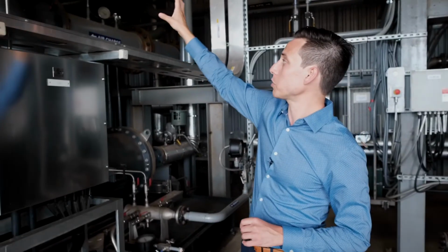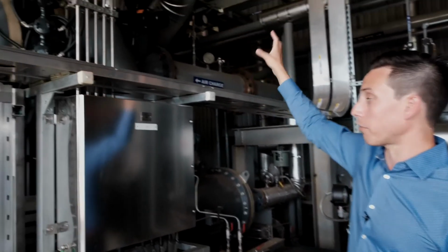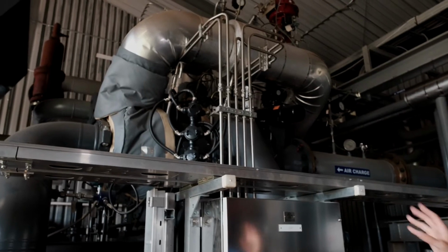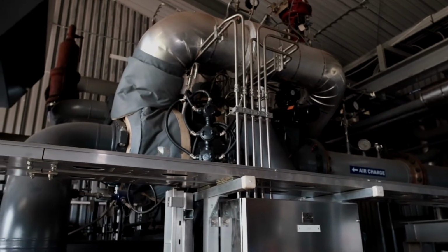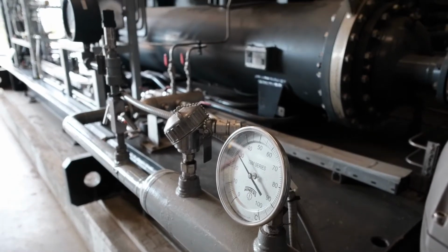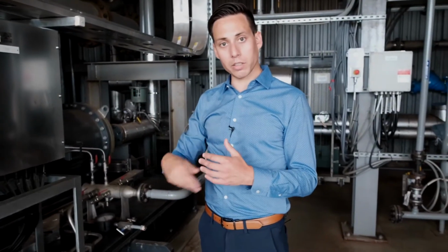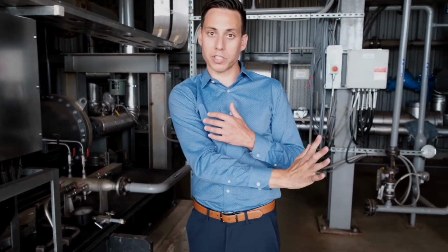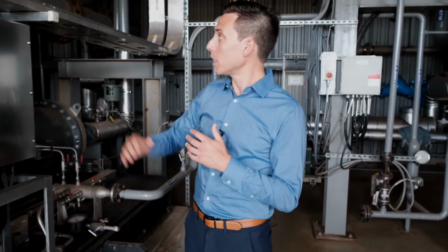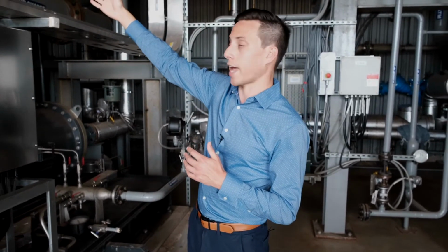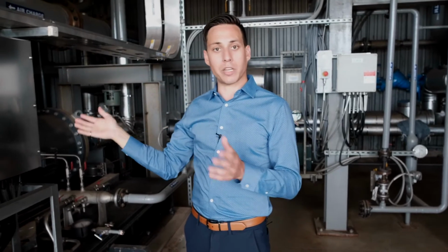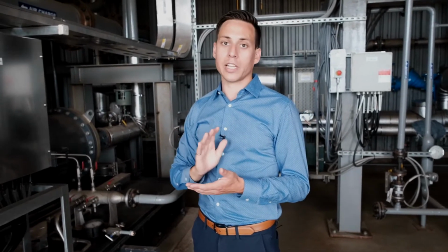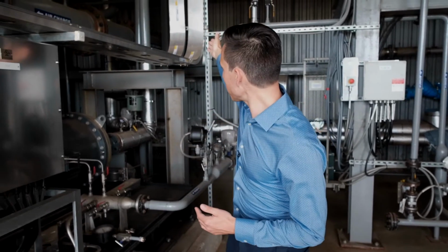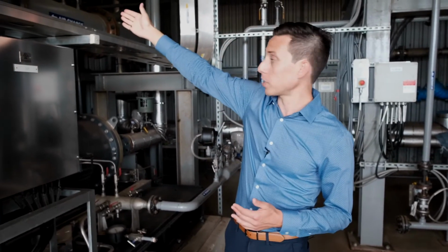Each impeller is housed in each one of these casings. There are 5 casings and 5 impellers, hence, this is a 5-stage machine. Each impeller is a highly engineered fan blade. By spinning, it draws air in from one side and forces it out the back, moving much faster. In each one of these spiral scrolls on the outside of a stage, that speed is slowed down, converting the energy into pressure and heat.